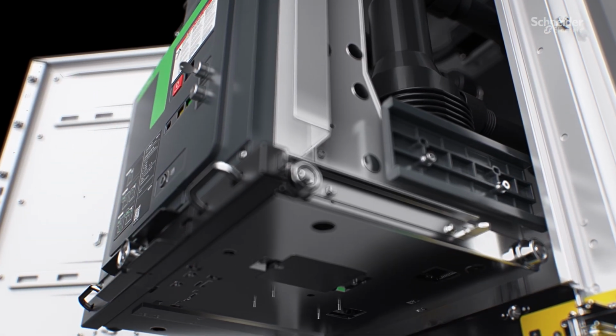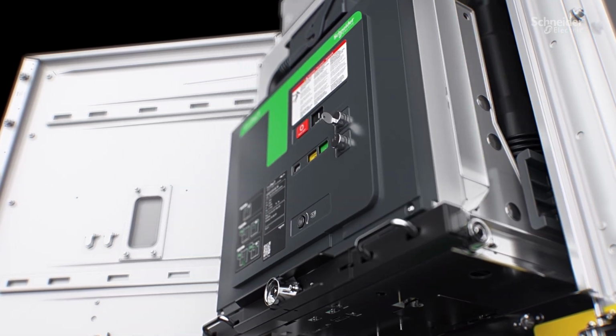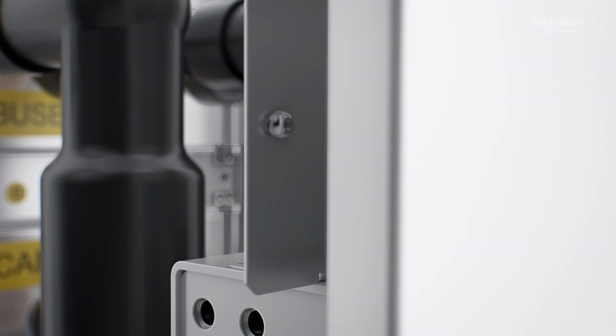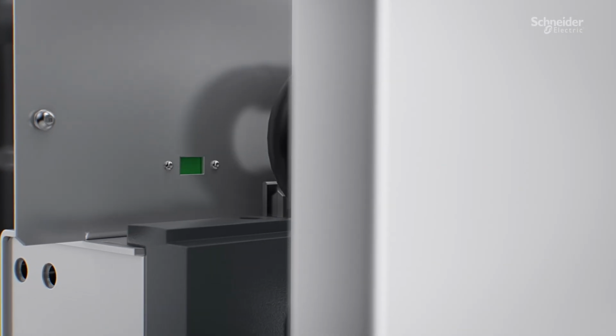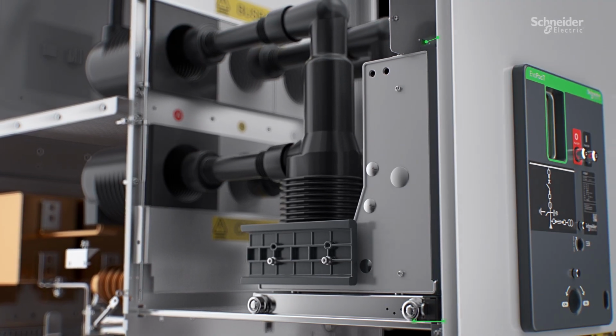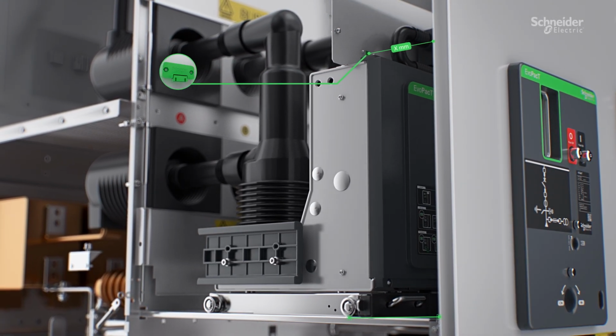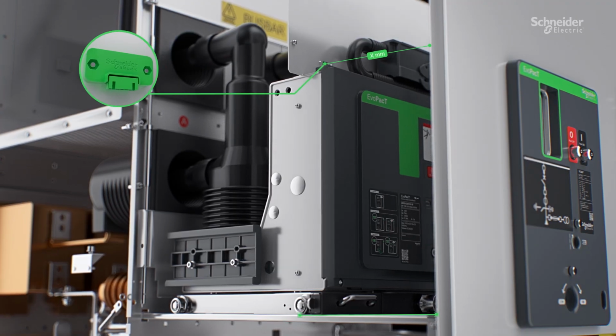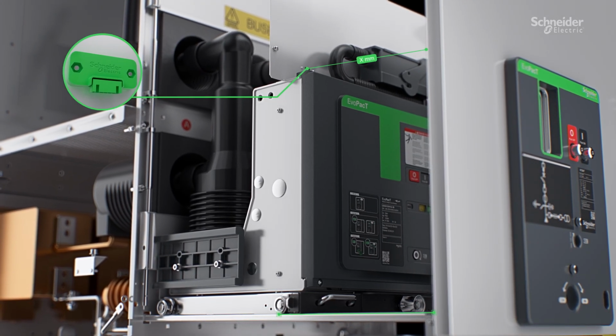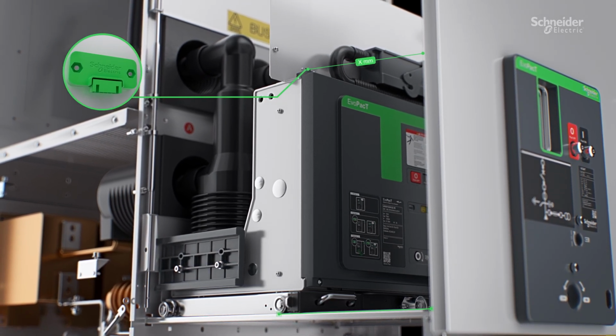When breakers are racked in, any misalignment can increase arc flash or fire risks. Two types of monitoring help identify and avoid those threats. The alignment sensor measures the position within the circuit breaker compartment to ensure MV contacts are inserted correctly.